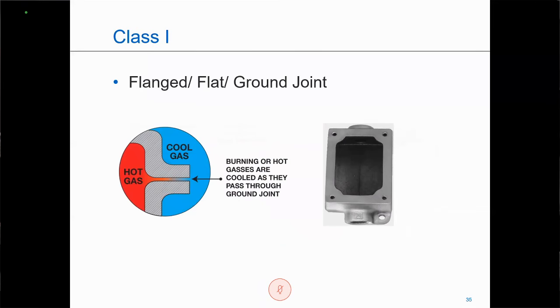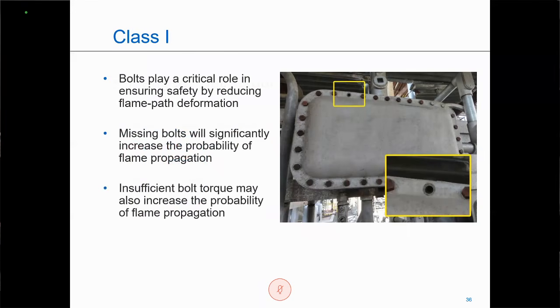For a control station such as this, typically people aren't questioning the installation of the bolts. It's only 4 bolts. But when I get to the larger units, the large junction boxes, the motor starters, the panel boards, and we start seeing 20, 30, 40 bolts, here's when I get people asking the question, can't we just put 1 bolt in each corner? I'm getting in and out of this unit, and I'm tired of opening and closing all these bolts. Well, these bolts maintain the flame path integrity, and without them, the gases could escape hot and ignite the surrounding gases and vapors and cause a large explosion within the facility.